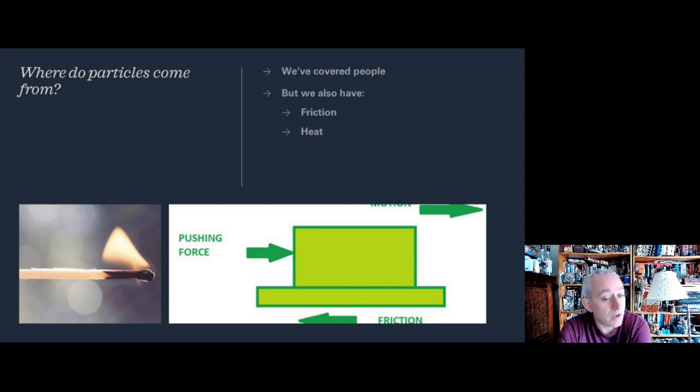There's friction between skin and the clean room suit, and walking produces friction. Friction tends to produce larger particles above five microns in diameter. We know this from when trays are slid, for example loading a UDAF cart or manually loading a freeze dryer - we get elevation of five micron particles.